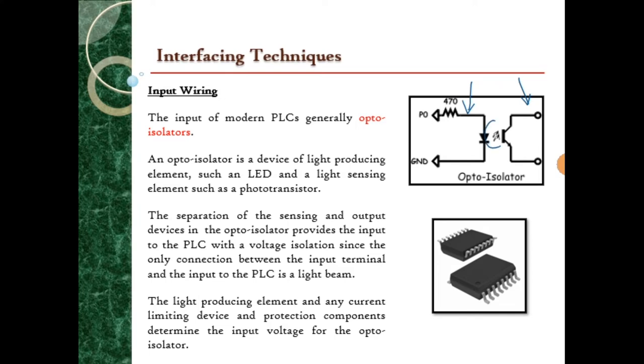It does this by using light. An opto-isolator is a device with a light-producing element such as an LED and a light-sensing element such as a phototransistor. The separation of the sensing and output devices in the opto-isolator provides the PLC input with voltage isolation, since the only connection between the input terminal and the input to the PLC is a light beam. For example, this is the input terminal to the PLC, and this is the output or other devices. These are the two isolated circuits, connected by a light beam here.